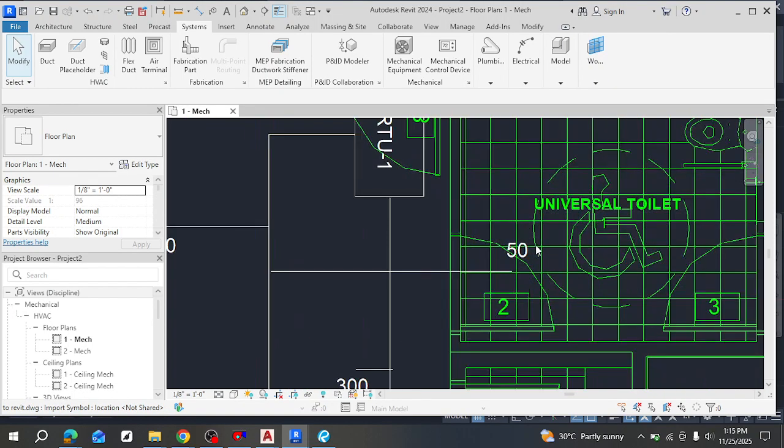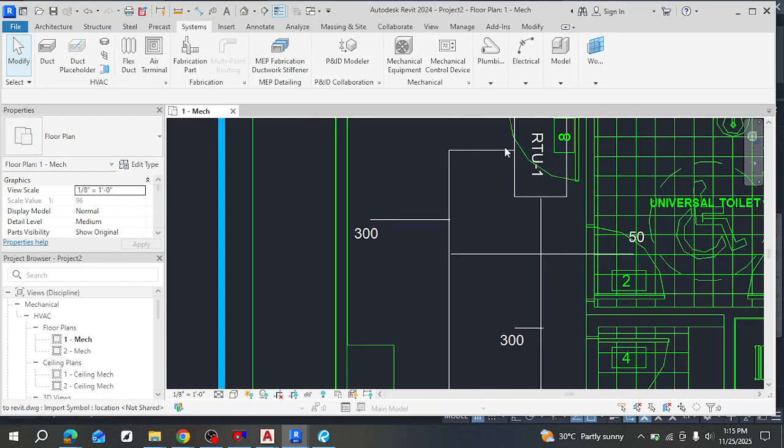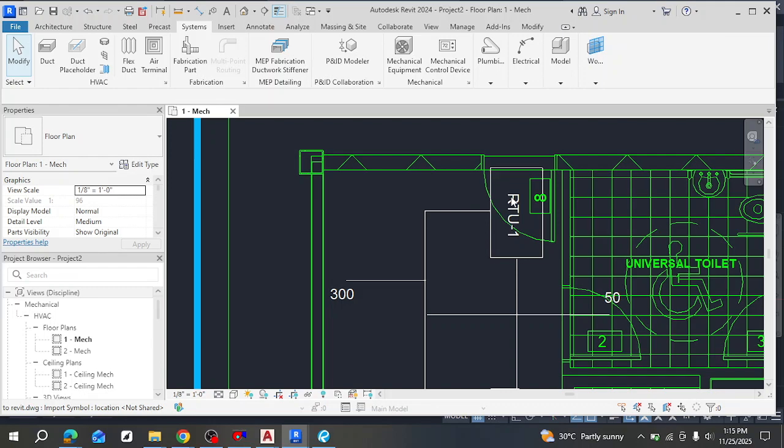Then you see that there's one going here that's 950. So that is 950. Remember that our total equipment size is supposed to give us roughly 1200. Our calculations give us 400 CFM for this space, but now we're overriding that with the information we got from Manual N. Manual N is like the energy load calculation for commercial buildings. So that is 950 leaving this.